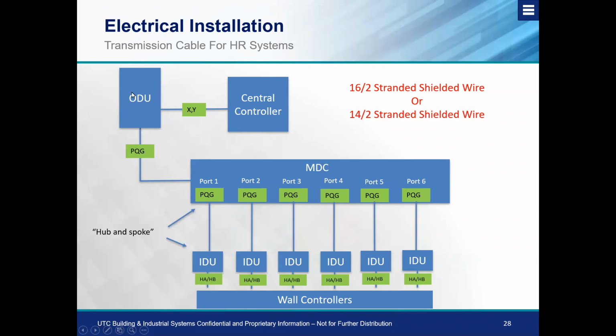Okay, so now we've established outdoor unit communication from outdoor unit to MDC. Now we have hub and spoke. Depending on the amount of ports that you have on the box, in this case our smallest box is a 6-port, we have each individual PQG port: port 1, port 2, port 3, port 4, etc. All you're doing is going from port 1 to indoor unit 1, port 2 to indoor unit 2, port 3 to indoor unit 3, etc. So now we don't have that daisy chain that's going to come across here, which can often be miswired. Essentially, you can follow your control wire right along your equipment directly to that indoor unit, and that hub and spoke style communication wiring makes the wiring of the system simplistic.